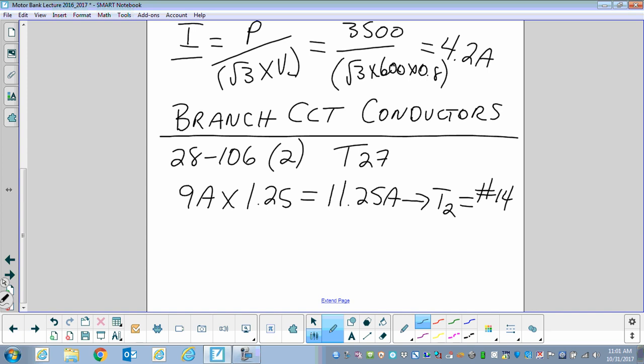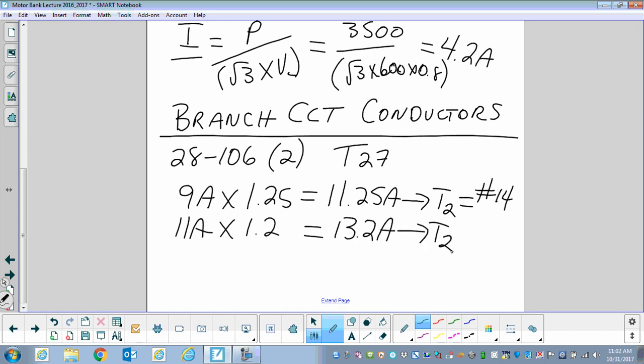The next motor is a non-continuous duty motor — short time duty, 15 minutes. We take that 11 amps to Table 27 to find the multiplying constant. Short time duty at 15 minutes gives us 1.2, or 120%. So 11 amps times 1.2 equals 13.2 amps, and from Table 2, that also equals a number 14 wire.